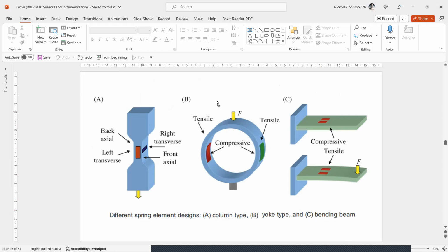In figure B, in the middle of the slide, we have a ring or yoke type spring element. Here the four strain gauges, two inside compressive and two outside tensile, can all be mounted in a differential mode. We now have two compressive and two tensile gauges, with almost equal but opposite sensitivity for the applied force. For this arrangement, the full benefit of the advantage of the full bridge is achieved.